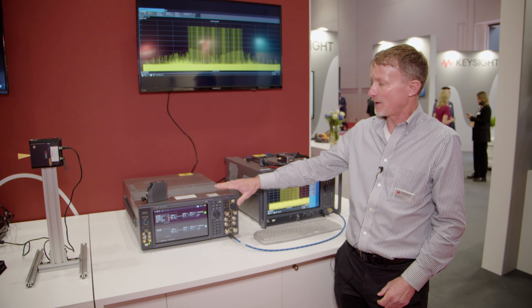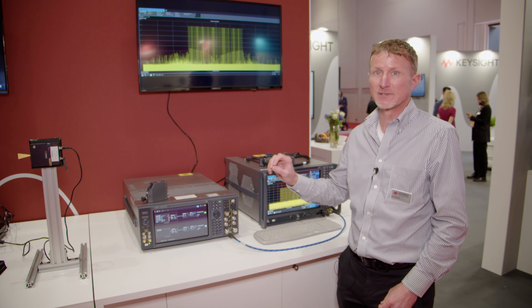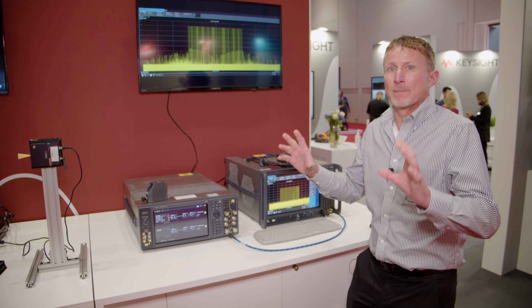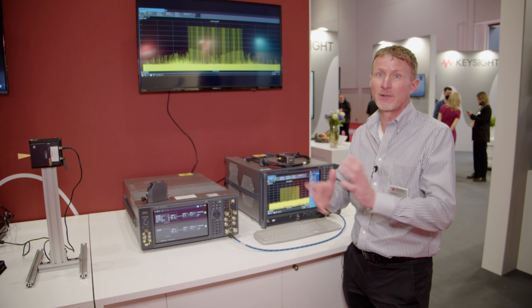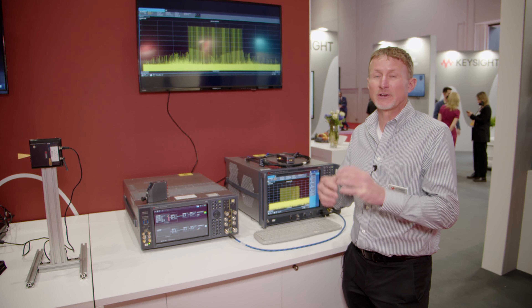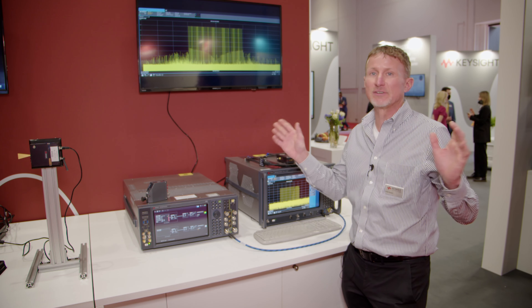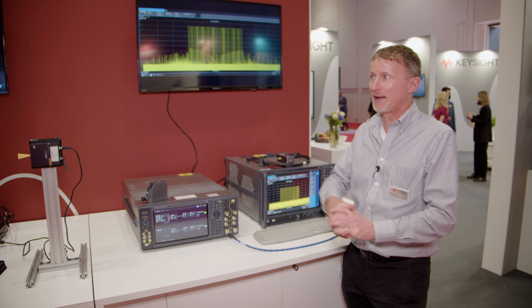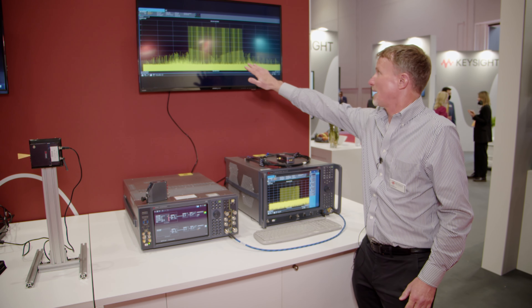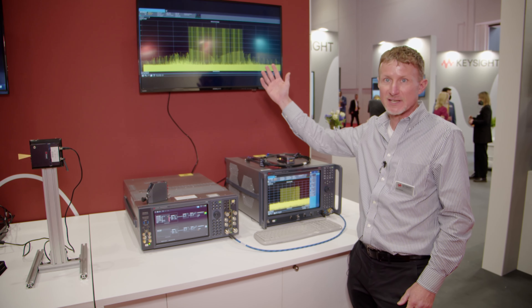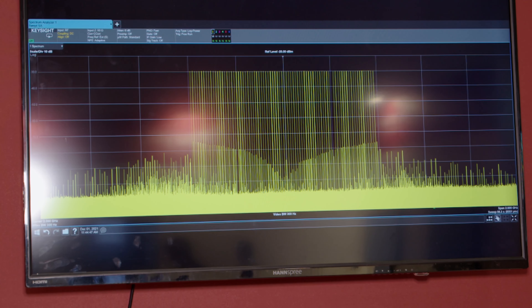To start, I'll show you a couple of the new features of the VXG by generating a very simple multi-tone signal. Before I show you the results of that, I'd like to show you the results of a traditional vector signal generator using an IQ modulator architecture — this is what every signal generator on the planet uses today. If you look at the top screen here, you can see that multi-tone signal.